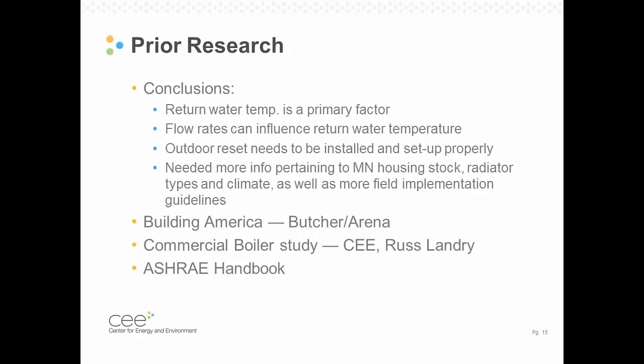We did look at some prior research on condensing boilers. All of these are cited in our final report that will be coming out soon. And generally, they all had similar conclusions. The return water temperature, again, was the primary factor in determining efficiency rates. Flow rates can influence that return water temperature, so how fast the water is moving through the distribution system was a finding from these projects. The outdoor reset control, which really controls the modulation capacity of a boiler, needed to be installed and set up properly in order to get the efficiency. This was a finding from a research project out east. And we felt we needed a little bit more information pertaining to the Minnesota housing stock and radiator types and climate, and then just some more examples of field performance. So here are a few of the projects that we looked at.